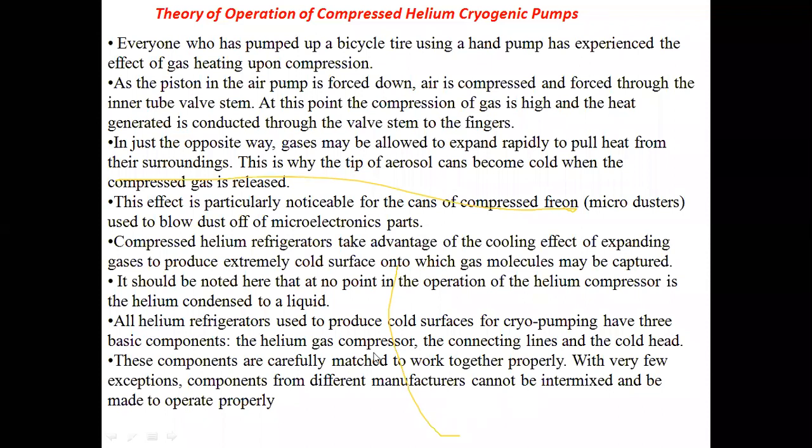All helium refrigerators used to produce cold surfaces for cryopumping have three basic components: the helium gas compressor, the connecting lines, and the cold head. Obviously the compressor is required for any type of refrigerator. These components are carefully matched to work together properly with very few exceptions. Components from different manufacturers cannot be intermixed and made to operate properly.